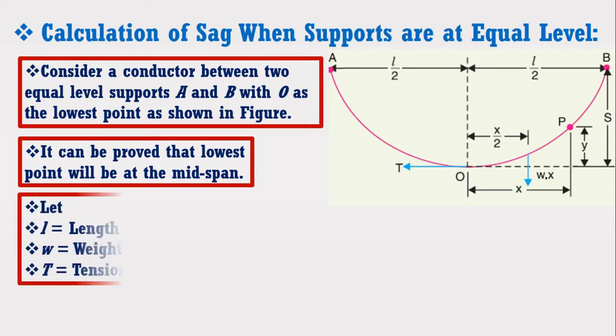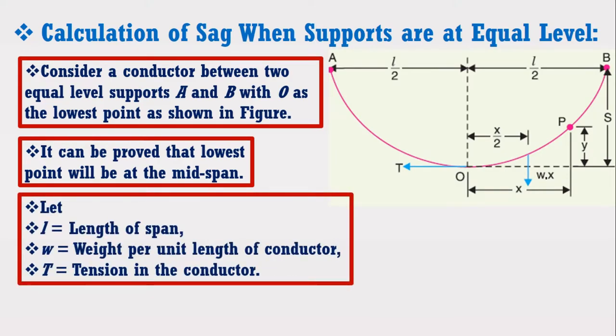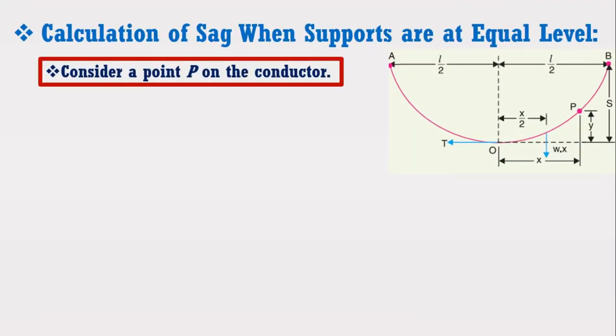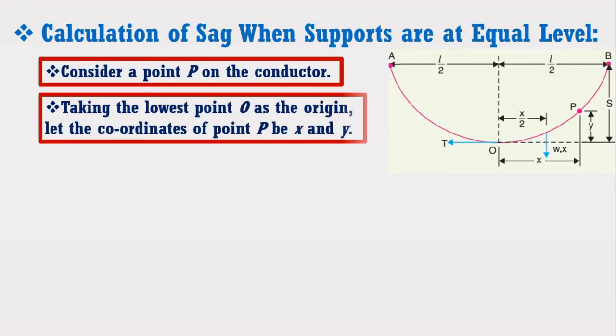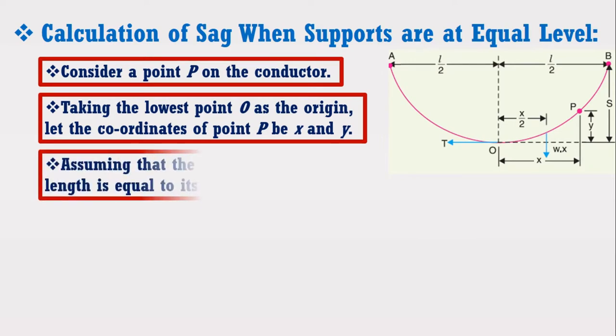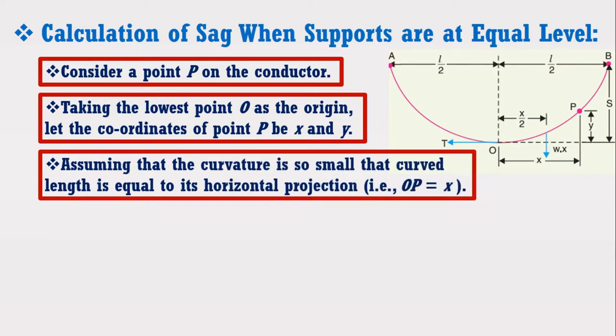Let L be the length of the span, W be the weight per unit length of the conductor, and T be the tension in the conductor. Consider a point P on the conductor, taking the lowest point O as the origin. Let the coordinates of point P be X and Y. Assuming that the curvature is so small that the curved length equals its horizontal projection, OP is equal to X.